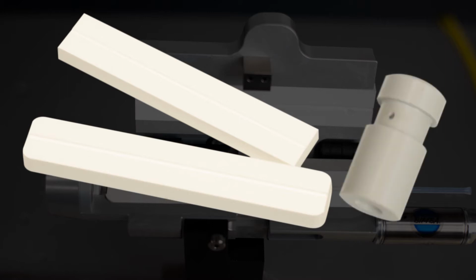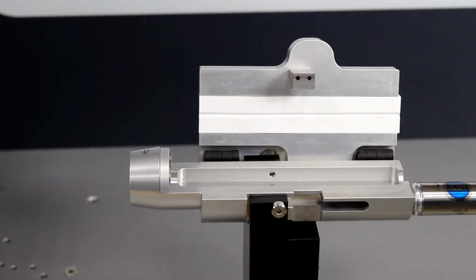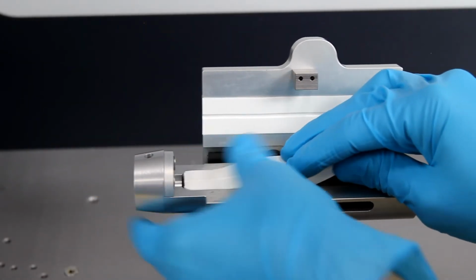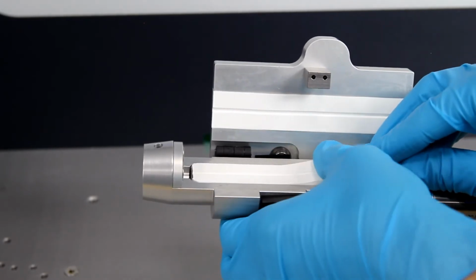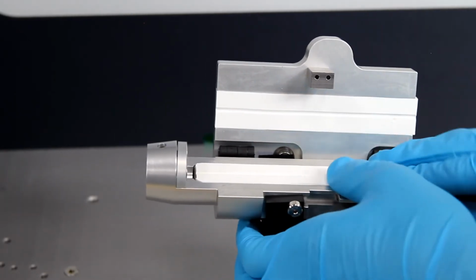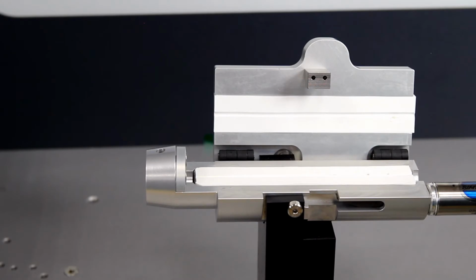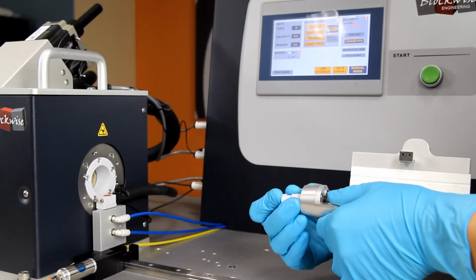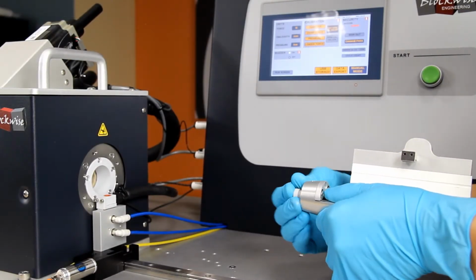The carrier will also need to have a custom sized alignment bushing. This will have a hole drilled in it that is also sized to the outer diameter of your catheter. If your machine has liquid nitrogen cooling, then the bushing will need to be stepped in order to allow the liquid nitrogen to reach the stent before it enters your catheter. Before using the clamshell gripper, you'll have to install the custom tooling. First, insert the rubber grippers, ensuring they're fully seated into the carrier. Next, insert the alignment bushing into the clamp on the front of the gripper.